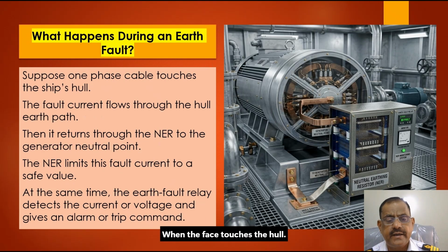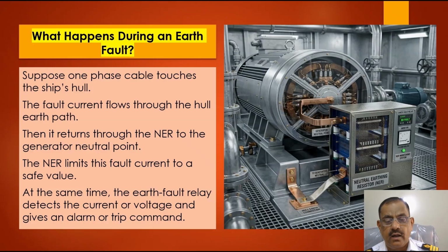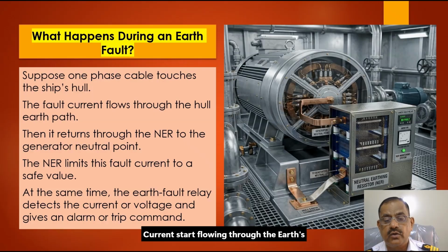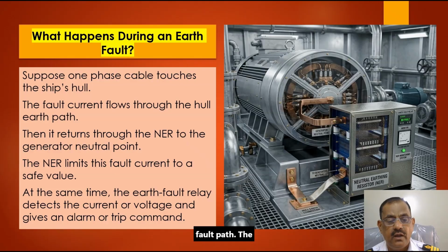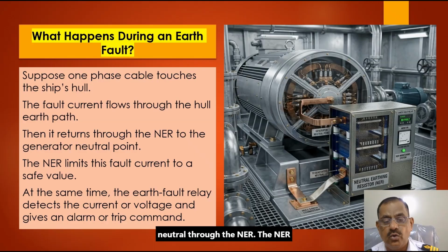When the phase touches the hull, current starts flowing through the earth fault path. The current returns to the generator neutral through the NER. The NER limits this current to a safe level. At the same time, the earth fault relay senses the fault and gives an alarm or trip signal depending on the protection settings.